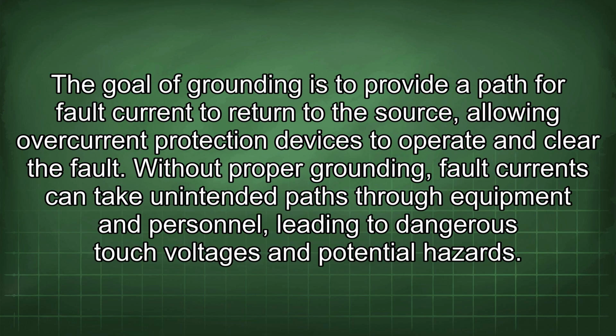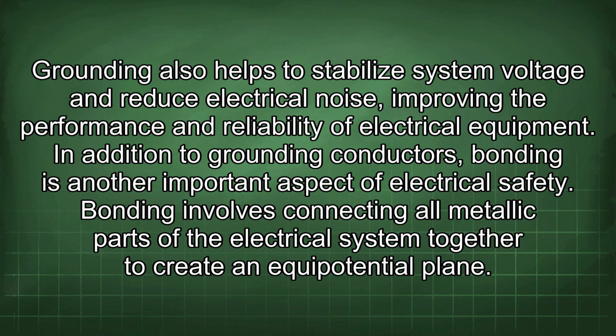The goal of grounding is to provide a path for fault current to return to the source, allowing overcurrent protection devices to operate and clear the fault. Without proper grounding, fault currents can take unintended paths through equipment and personnel, leading to dangerous touch voltages and potential hazards. Grounding also helps to stabilize system voltage and reduce electrical noise, improving the performance and reliability of electrical equipment.